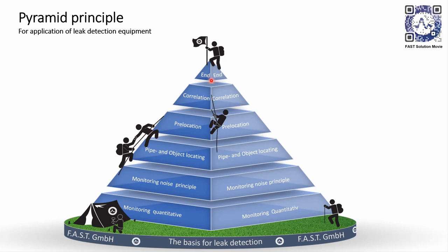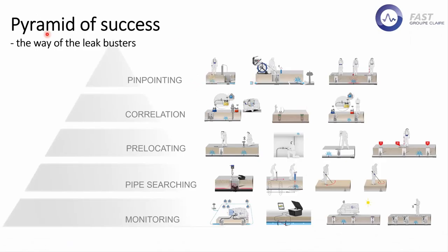Above that, we usually go in and do a correlation. That means we are able to really calculate the exact position of the leakage. On the top end, the real goal is always to pinpoint the leakage and know the exact position, so that we excavate only as much as needed for repairing the damage of the water network.